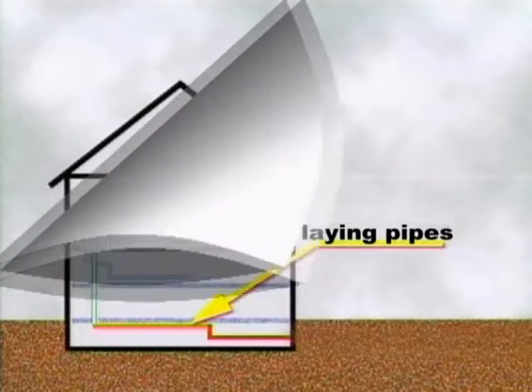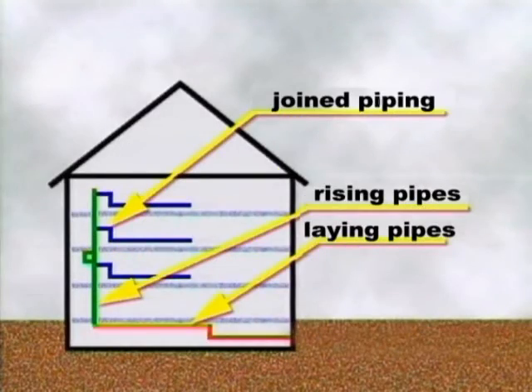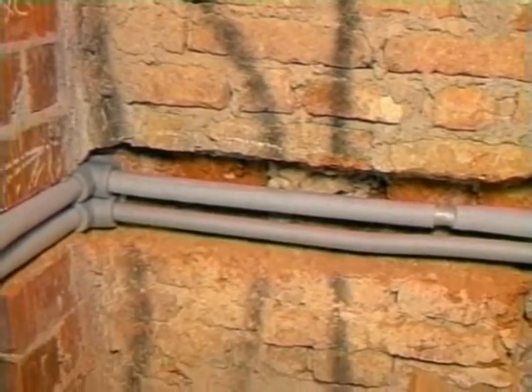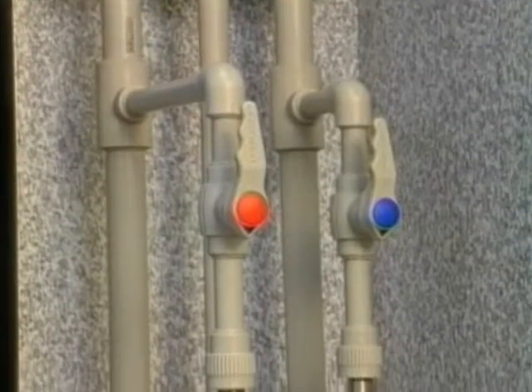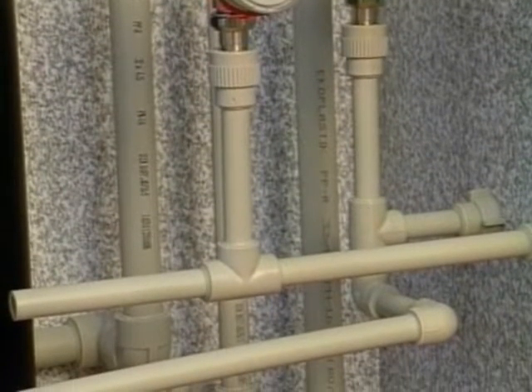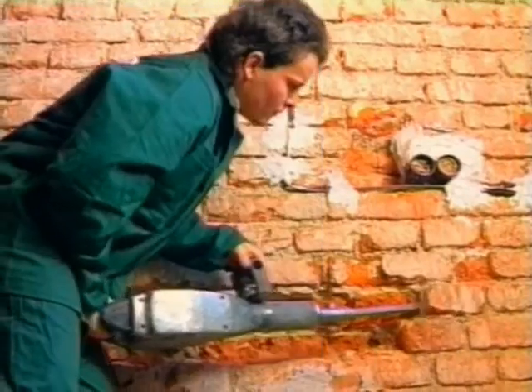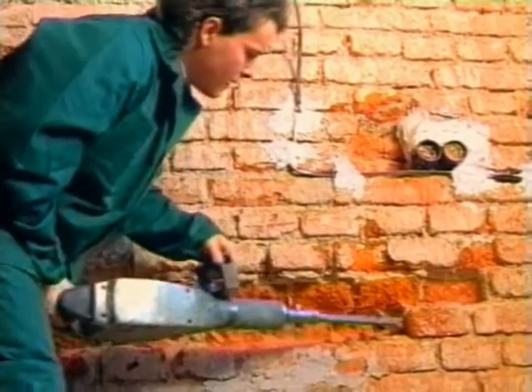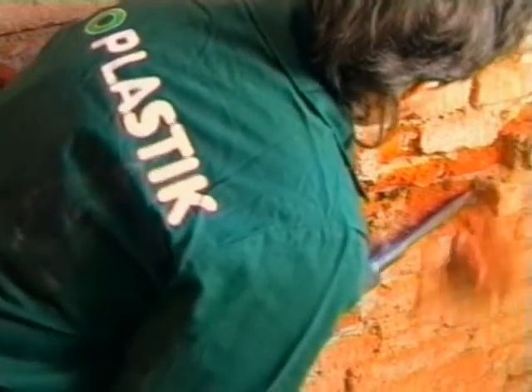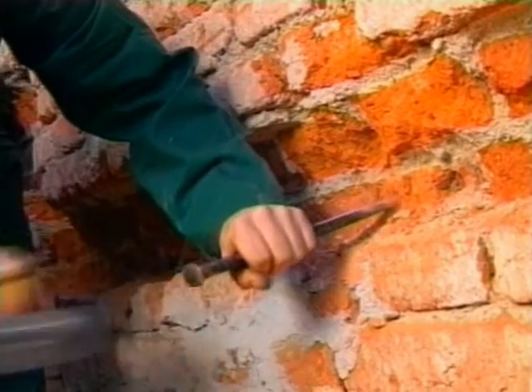Internal water piping systems are divided into 3 parts: horizontals, risers, and joining pipes. Joining and rising pipes are fed through loose brackets or installation partitions. Running pipes, particularly hot water pipes, along the walls is not suitable for aesthetic reasons and with regard to expansion. Horizontal pipes are often run along the ceiling or hidden from sight. Tracks must be big enough for the pipes, including insulation, to sit freely. Tracks should be cleaned first to avoid any mechanical damage to pipes and insulation during fitting and operation.